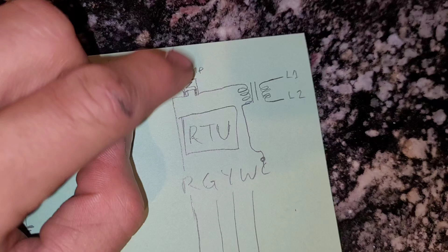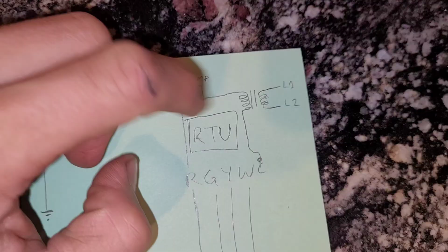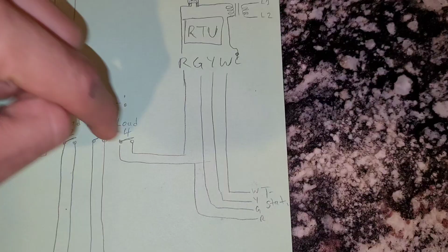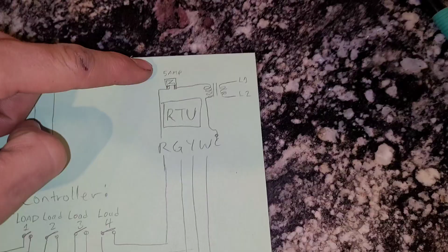On this one I drew what's going on inside of the rooftop unit. The R wire has a 5 amp fuse and the transformer is on this side. So the transformer sends power through the fuse first and then to the R wire and then down through the controller and to the thermostat, and if there's any problem on this end it will burn that fuse instead of burn out that transformer. What they had done, a couple of things.